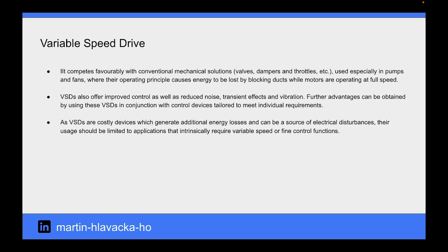VSDs also offer improved control as well as reduced noise, transient effects, and vibration. Further advantages can be obtained by using these VSDs in conjunction with control devices tailored to meet individual requirements. As VSDs are costly devices that generate additional energy losses and can be a source of electrical disturbances, their usage should be limited to applications that intrinsically require variable speed or fine control functions.